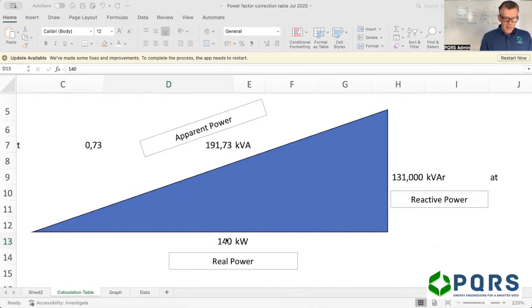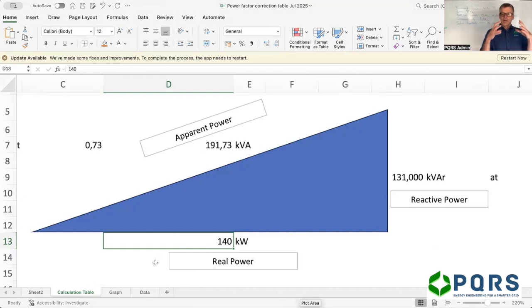So let's assume that it's a weekend and you are drawing 140 kilowatts. Your system shows a demand of 190 kVA. What I took actually comes out of your load profile. So it was a weekend load. Now, if I'm going to change the kilowatts at the bottom, let's assume you've got 100 kilowatts that's busy being pushed into the grid by the solar system, which means it's going to reduce your real power to 40 kilowatts. So I'm going to assume that 100 kilowatts is being supplied by solar. That reduces your load from the grid to 40.